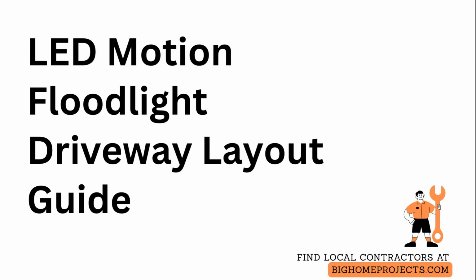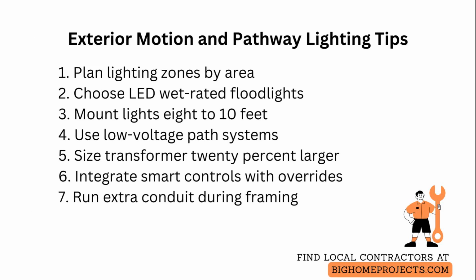Upgrading exterior motion sensor and pathway lighting during new home construction greatly improves safety, convenience, and deterrence. Start by planning lighting zones around entries, driveways, and walkways so each circuit serves a coherent area and minimizes unwanted activations. For motion sensor floodlights, choose light-emitting diode fixtures rated for exterior wet locations with adjustable sensitivity and timer settings.